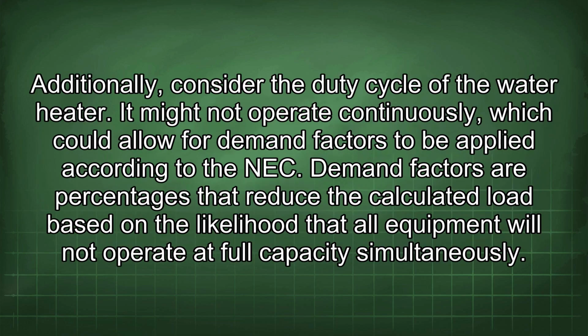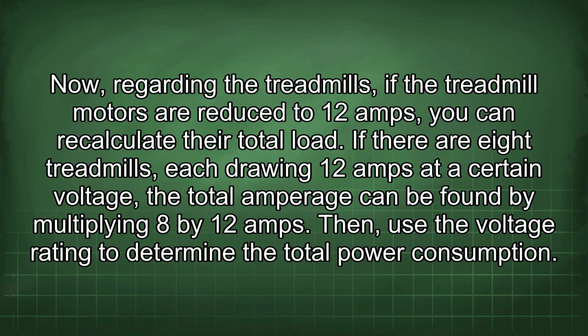Additionally, consider the duty cycle of the water heater. It might not operate continuously, which could allow for demand factors to be applied according to the NEC. Demand factors are percentages that reduce the calculated load based on the likelihood that all equipment will not operate at full capacity simultaneously. Now, regarding the treadmills, if the treadmill motors are reduced to 12 amps, you can recalculate their total load. If there are 8 treadmills, each drawing 12 amps at a certain voltage, the total amperage can be found by multiplying 8 by 12 amps.